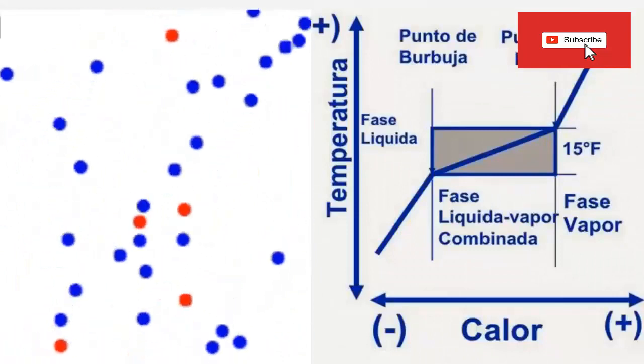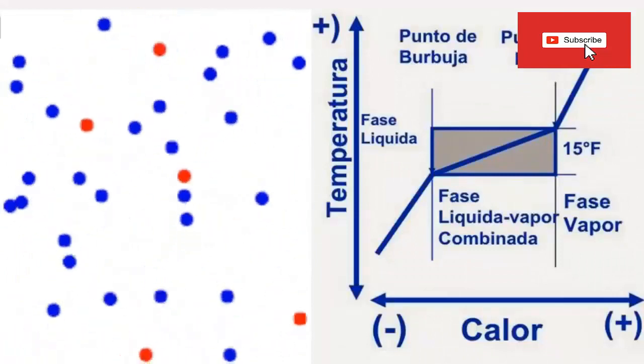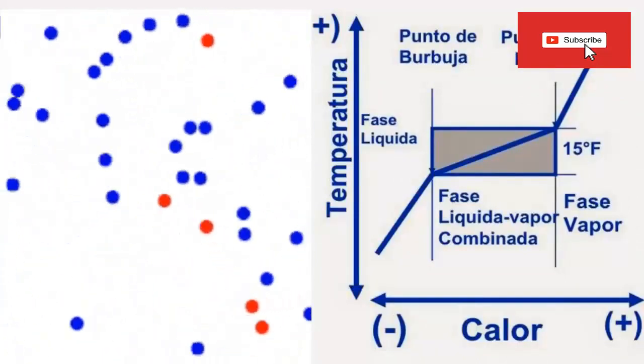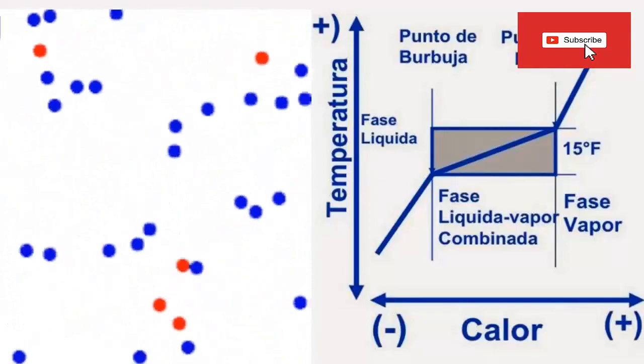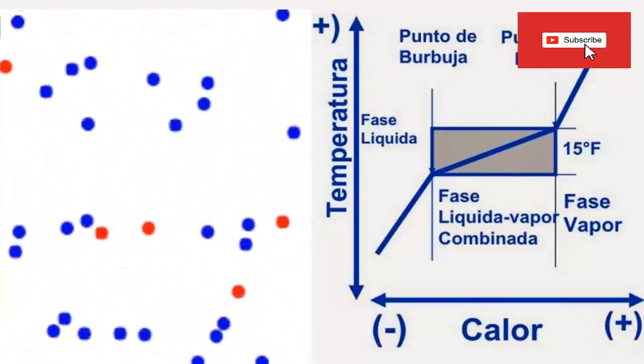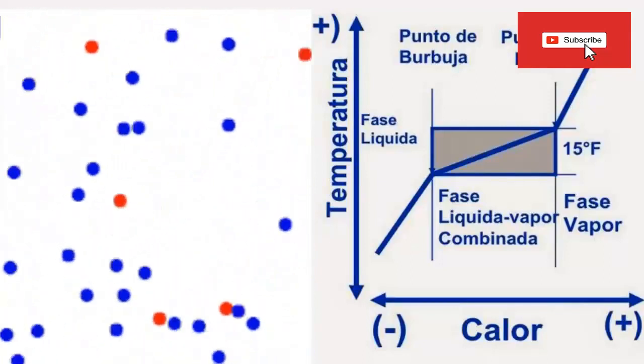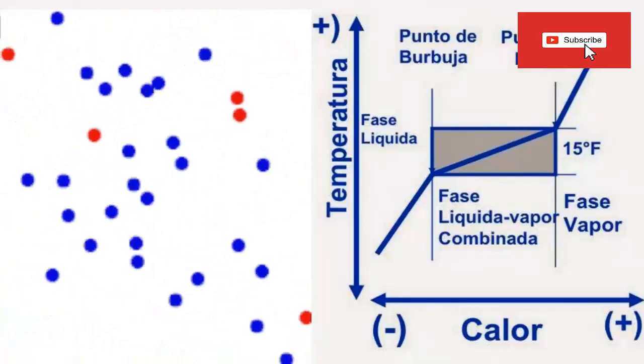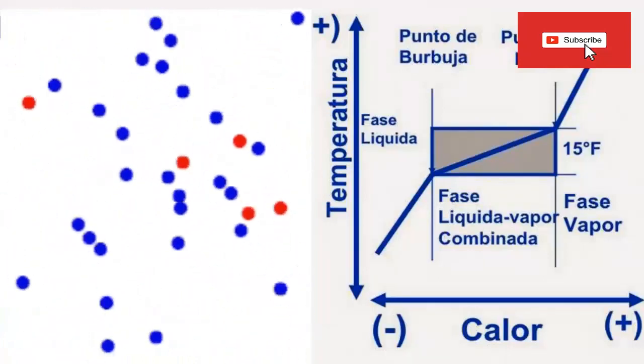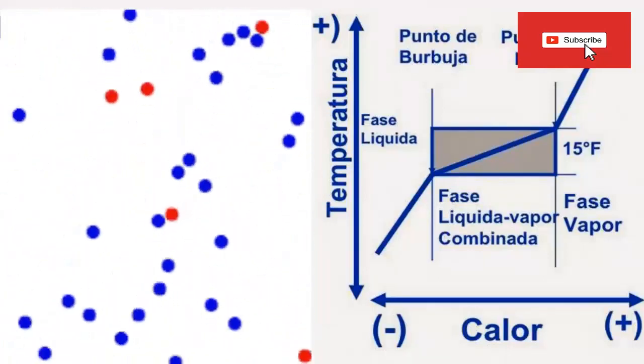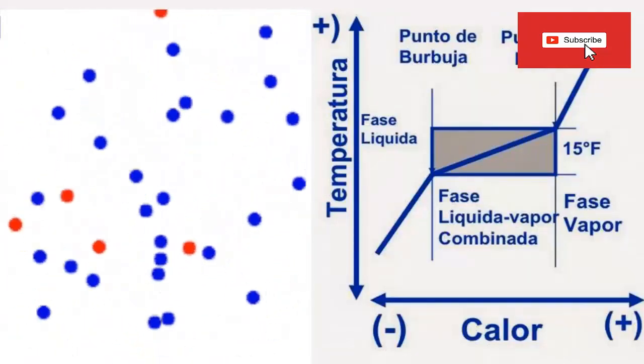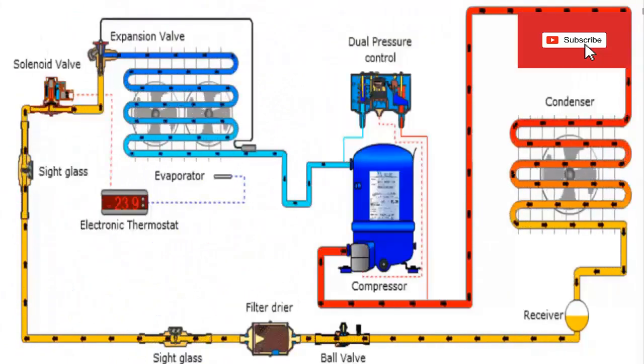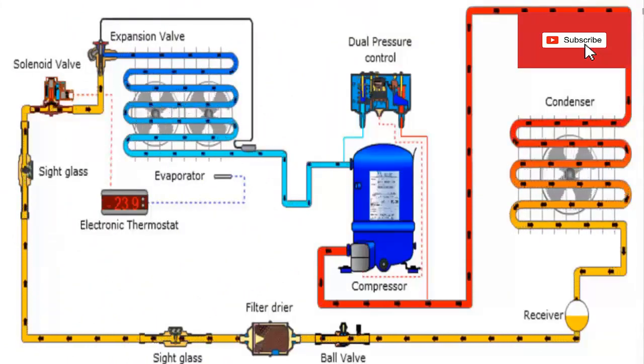Remember that glide means that the temperature of R449A changes while it is evaporating, and this aspect must be taken into account when recharging with R449A. To take this glide into account, we are going to carry out the following analysis.